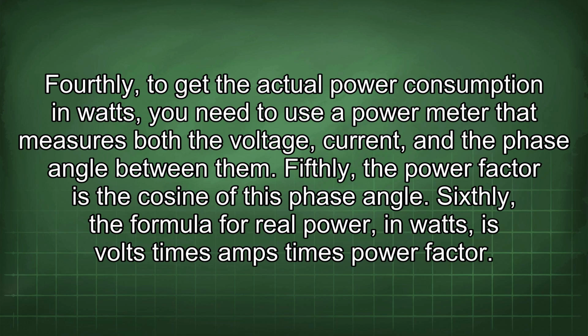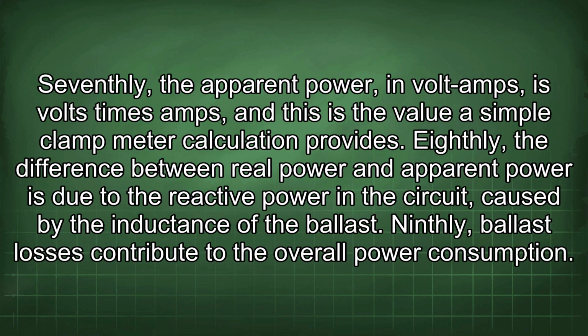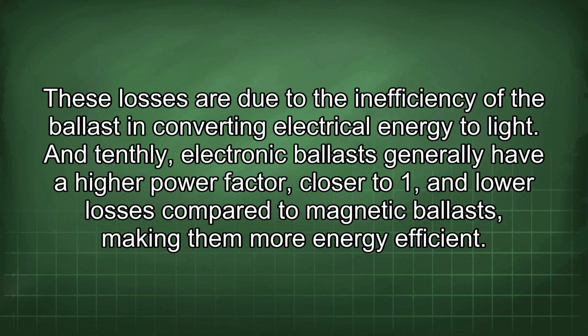Fifthly, the power factor is the cosine of this phase angle. Sixthly, the formula for real power in watts is volts times amps times power factor. Seventhly, the apparent power in voltamps is volts times amps, and this is the value a simple clamp meter calculation provides. Eighthly, the difference between real power and apparent power is due to the reactive power in the circuit caused by the inductance of the ballast. Ninthly, ballast losses contribute to the overall power consumption. These losses are due to the inefficiency of the ballast in converting electrical energy to light. And tenthly, electronic ballasts generally have a higher power factor, closer to 1, and lower losses compared to magnetic ballasts, making them more energy efficient.